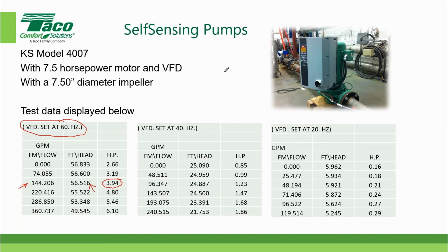So if the horsepower is 1.47 and the speed is 40 hertz, I guess the GPM is 143.507 and the head is 24.5. Right. And the pump can keep track of its own speed and its own power consumption. It simply looks up the data that we previously stored inside the computer, inside the drive. So that's how it works. It's as simple as that.